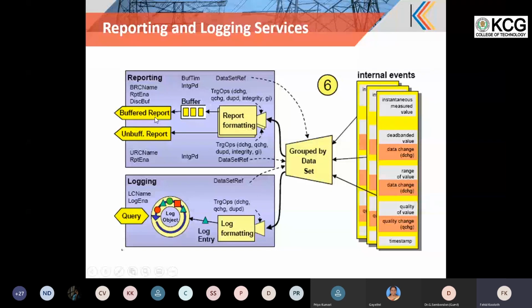That is a report. Log, again the similar trigger condition, based upon that a snapshot is taken, it enters the log buffer and it will not be automatically sent out to the client. If there is a query, the corresponding logs will be retrieved and sent out to the client. So that is the report control block and log control block detail.